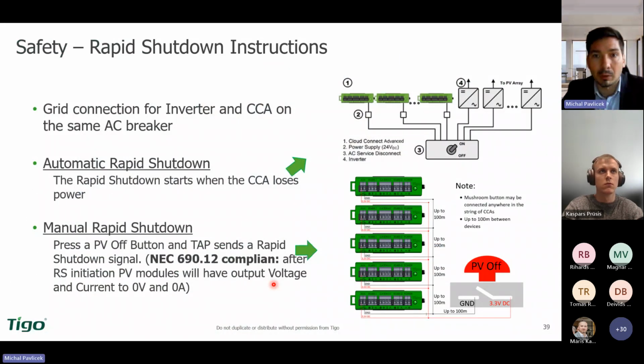For rapid shutdown control, you have two choices. One choice, and this is what is now shown on the picture, is to connect a switch or whatever contactor to the aux port. You can even connect, because if you have a big project and you have more CCAs, you can connect them all in parallel, or you can connect one button to each to be able to switch off each individual CCA individually.